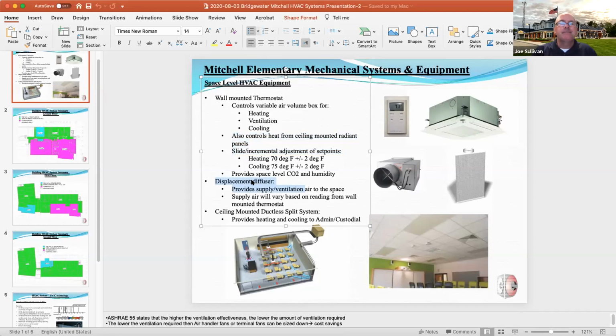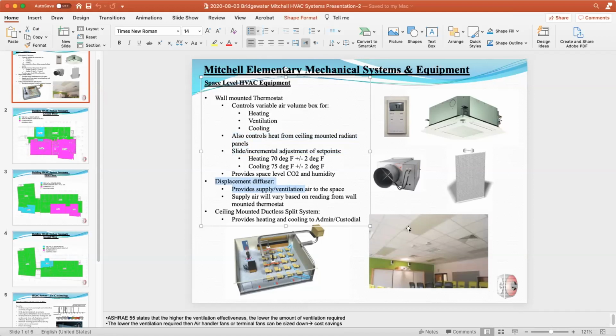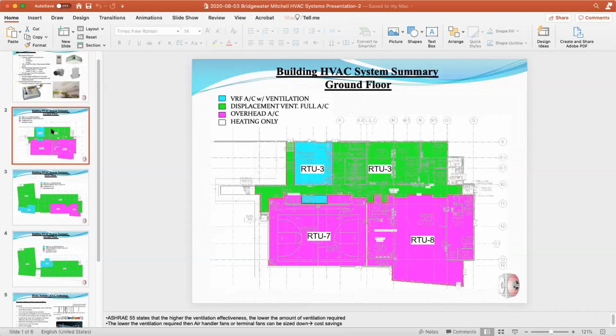I'll continue with the displacement diffuser. I mentioned we're supplying ventilation into the space, and then we're exhausting high. The other system I would like to talk about is the VRF, variable refrigerant flow systems. That's at the upper right, and that's within the administration and media center areas. So that's what's doing heating and cooling in those areas. There is supplemental hot water heating in those areas. And then those areas are getting the ventilation from a dedicated outdoor air rooftop unit, which would be 100% outside air. So again, pretty much in line with ASHRAE recommendations, where you've got 100% outside air to the spaces.